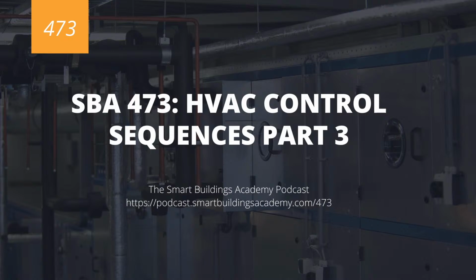So from there, right, we have our heat, and that's all well and good. We've got heat, we've got cooling, but then we have this thing called ventilation. What is the purpose of that? Well, sometimes you've met your set point. Set point's great, right? You're hitting 65-degree discharge air, you're using Economizer, everything's all well and good, but you still need airflow, and that is where ventilation mode comes in, and it simply circulates airflow in order to provide airflow to the space as needed, or spaces as needed.